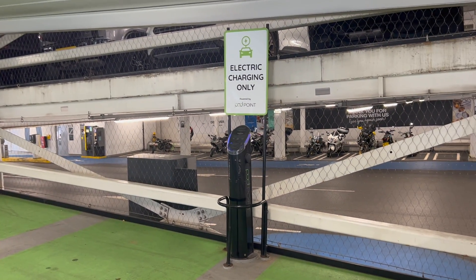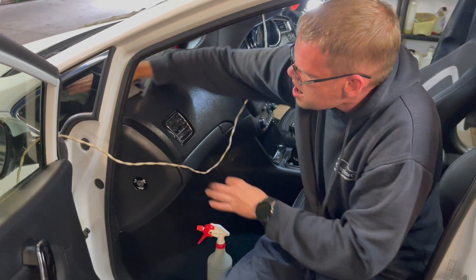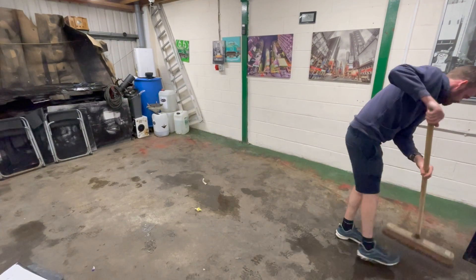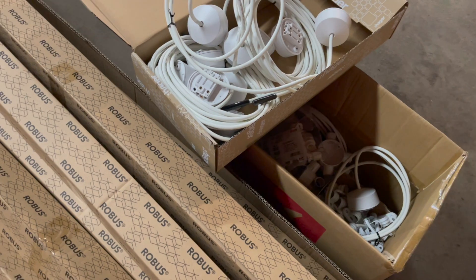The question we always get asked is how to determine the correct lighting levels for an application. The Society of Light and Lighting publishes comprehensive lighting guides giving suggested levels and parameters for a huge range of applications, from offices to car parks. For detailed work such as car valeting, we need to be looking at around 700 lux. However, you don't need 700 lux all the time — some initial cleaning and polishing isn't detailed work. So we'll arrange lighting across two circuits: with both on we get 700 lux, with one circuit 350 lux — a 50% reduction in energy.